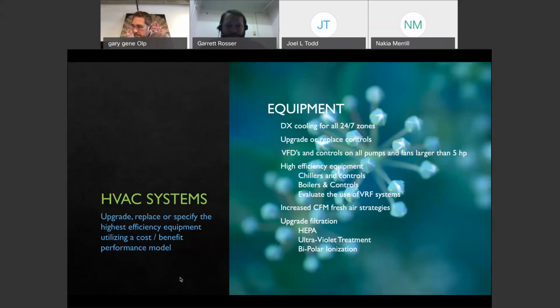High efficiency equipment in terms of chillers and their controls, boilers and their controls, and also looking at the use of VRF. It kind of got a bad rap as it was rolled out in the industry. But I think if the installation is correct and we're using brazed joint connections on all refrigerant piping, and you follow the manufacturer recommendations, some of them require that you do not use a sight glass, that you do not use filter line dryers. So that is a deviation from kind of the norm on DX installations. And certainly all you techs out there have to be charged positively with nitrogen.